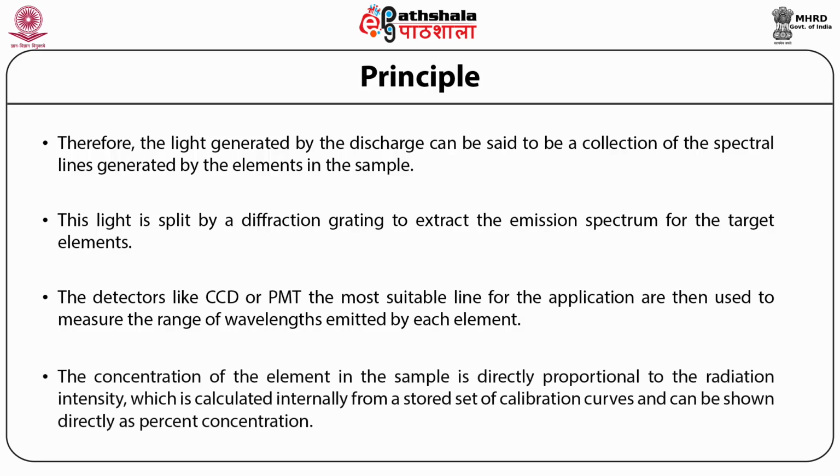The concentration of the element in the sample is directly proportional to the radiation intensity, which is calculated internally from a stored set of calibration curves and can be shown directly as percent concentration.